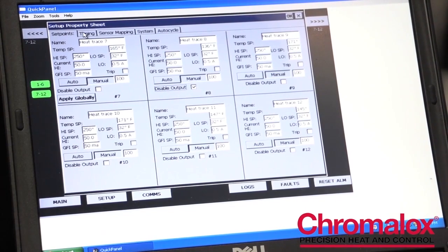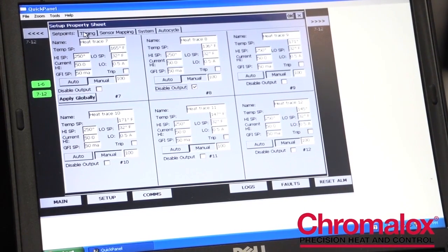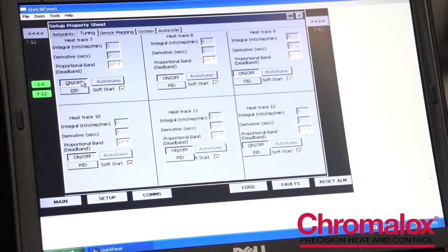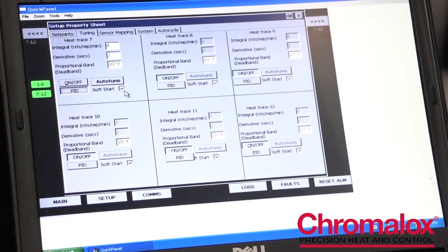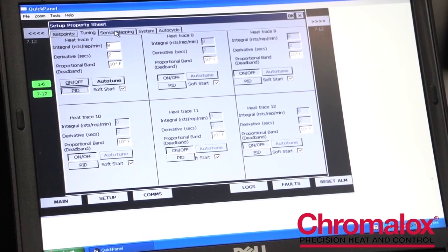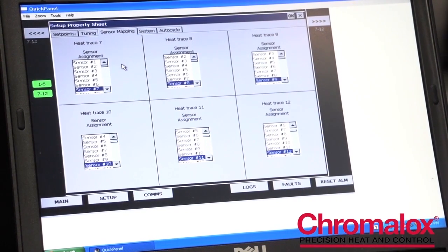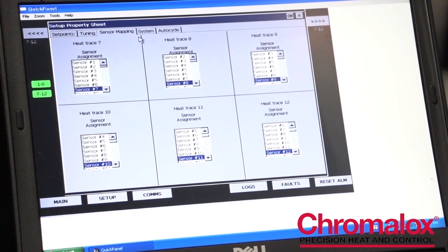The next tab is the tuning tab. In the tuning tab, you can choose how the control manages the heaters — whether it's an on-off control or PID control. This is also where you can select your soft start function, or turn it off if you have a non-heat trace application. We also have a sensor mapping feature on our ITLS and ITAS panels, where you can map more than one output to an individual sensor, which provides a lot of flexibility for the owner.